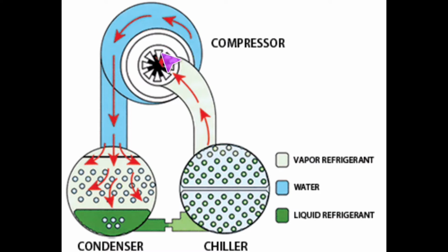So this is just a very basic, very crude setup in a lot of ways, but it gets the point across, right? So this is essentially what's happening here. This is our evaporator. We're pulling off through the suction volute. These are your little guide vanes right here. This is your impeller for the compressor. And then we're coming out the discharge back into the discharge line, into the condenser. We then use the condenser water to condense the liquid down. We come through an orifice here and then back into the evaporator.